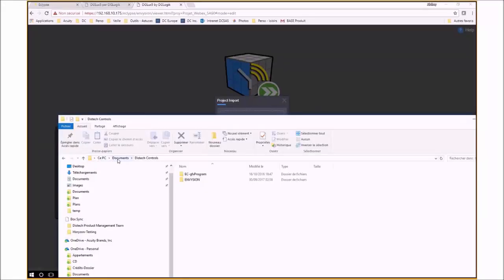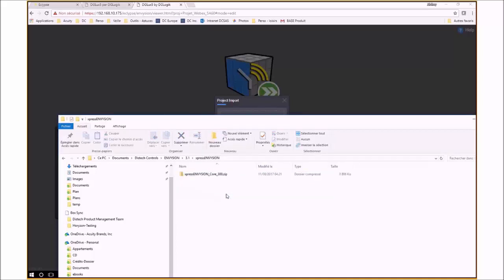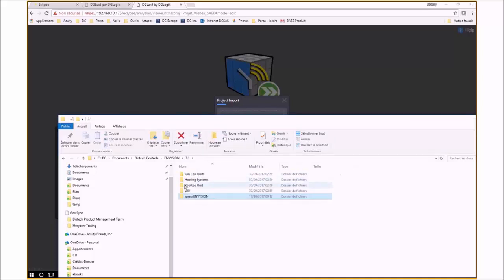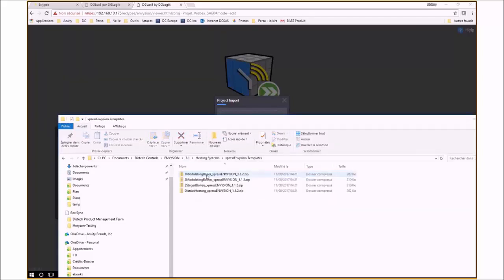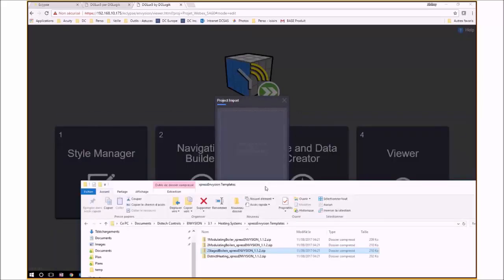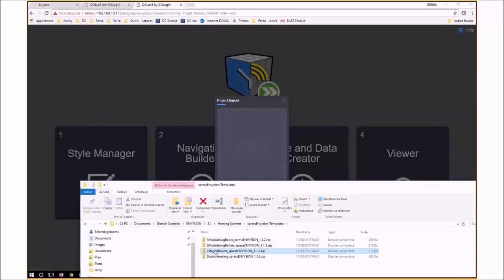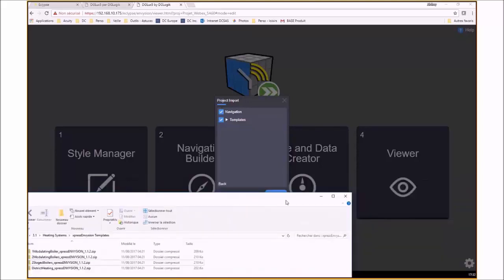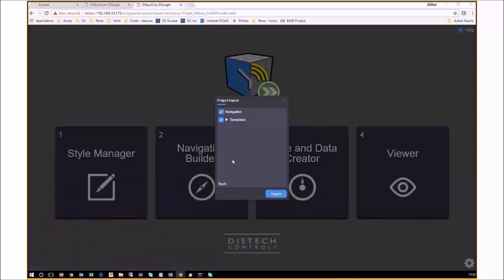To find the preloaded graphics for this application, open the file directory on your computer and you will find it in the Documents folder under DISTECH Controls. In here, you open Envision then 3.1 and here you will see your available projects. Since we are looking for boiler room graphics, we will go into Heating Systems, Express Envision Templates and locate the two-stage boilers.zip file. We can now select the file, drag it over to our Express Envision interface and drop it directly into the Import File Wizard. To complete importing the preloaded graphics, we will click on Import which takes us back to the Express Envision page.